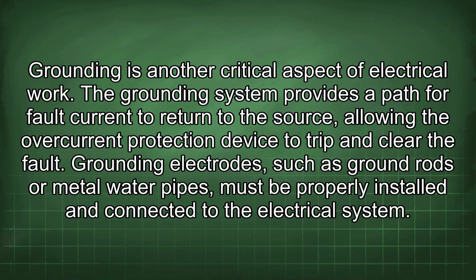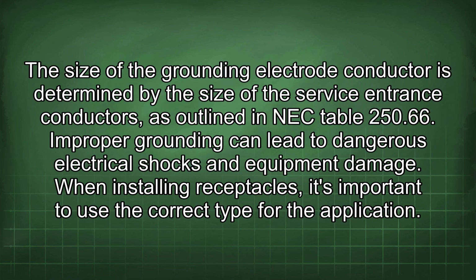Grounding is another critical aspect of electrical work. The grounding system provides a path for fault current to return to the source, allowing the overcurrent protection device to trip and clear the fault. Grounding electrodes, such as ground rods or metal water pipes, must be properly installed and connected to the electrical system. The size of the grounding electrode conductor is determined by the size of the service entrance conductors, as outlined in NEC Table 250.66. Improper grounding can lead to dangerous electrical shocks and equipment damage.